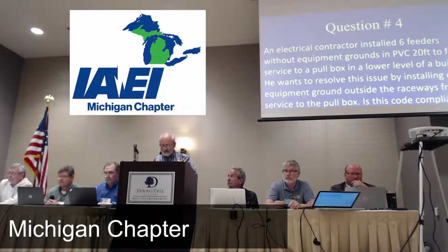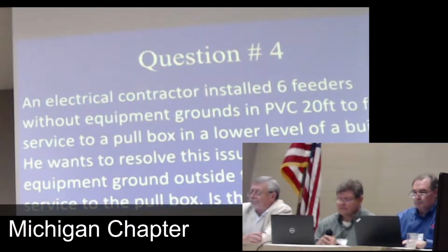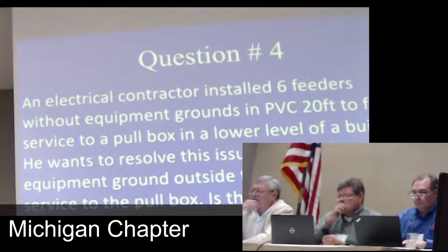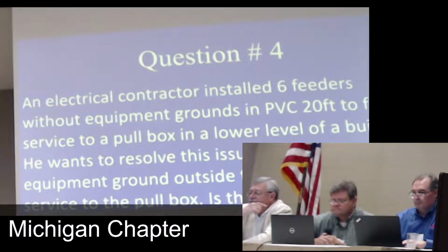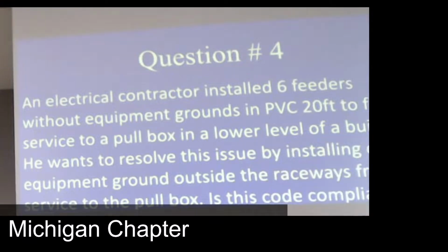Okay, Tim? An electrical contractor installed 6 feeders without equipment grounds in PVC 20 feet from the service to a pull box in a lower level of a building. He wants to resolve this issue by installing 1 equipment ground outside the raceways from the service to the pull box. Is this code compliant? No, it's not.